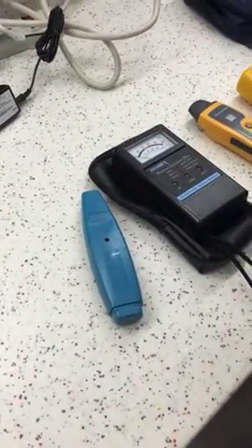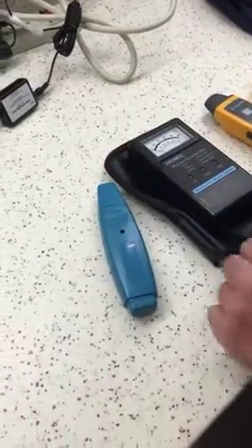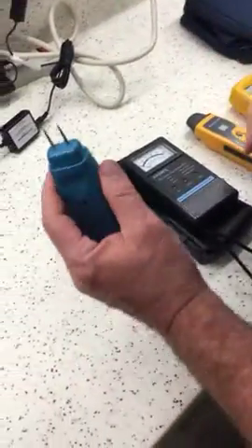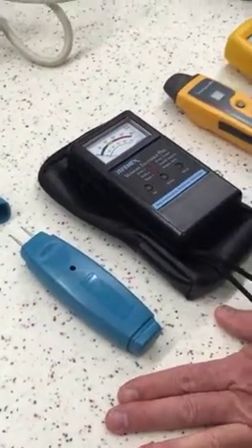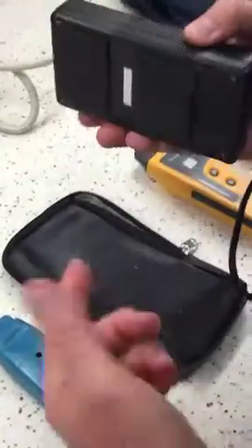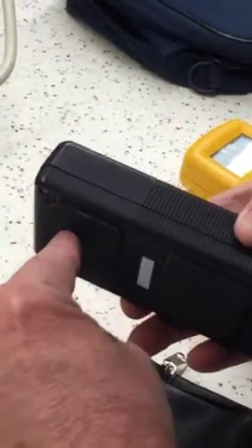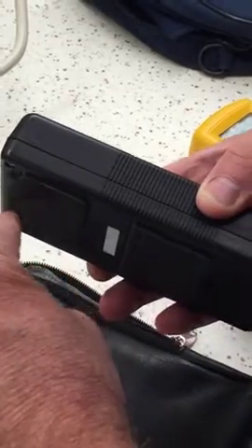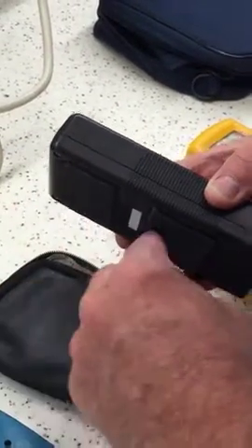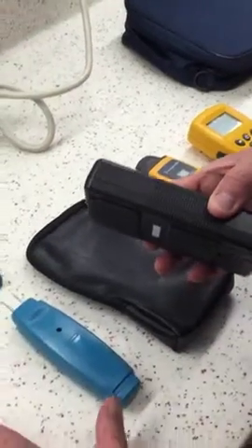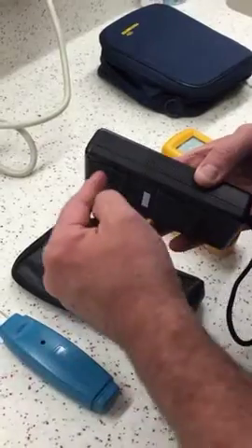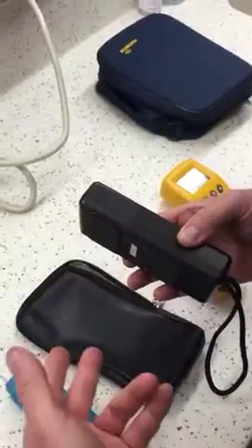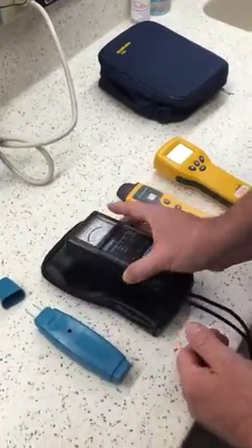One is a conductivity type that has two pins or needles. Here's an example of two of those pins. And then the other type is called a capacitance moisture meter. It either has a couple of pads that measure the capacitance of a radio signal that is sent out into the surface so that it reads down into the surface. If there's moisture in the material, it will change that signal, and that change in signal is proportional to the concentration of moisture that's in the surface.